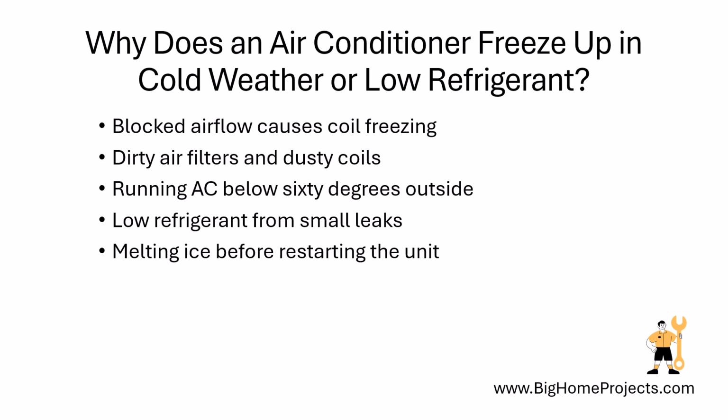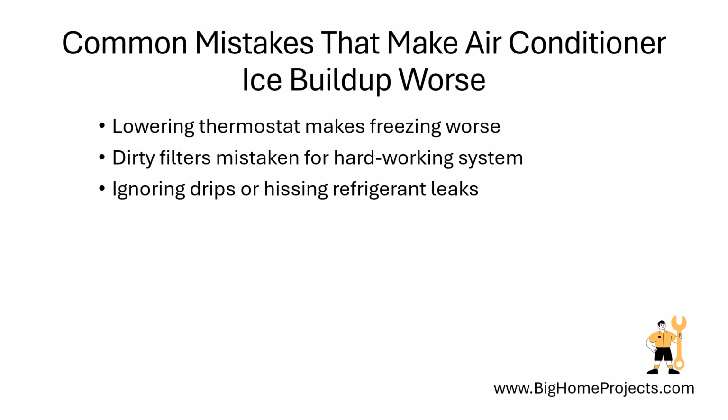The best first step you can take today is to turn off your system. Let the ice melt completely and check your air filter, since a dirty filter causes a huge percentage of these issues. One common mistake is turning the thermostat down even lower when you notice ice, thinking it will cool the house faster, but that actually makes the freezing worse, so instead turn the unit off completely until it thaws.